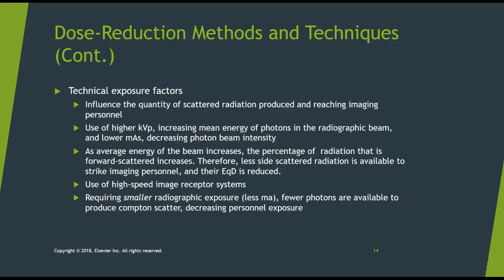Okay, another way you can reduce scatter is technical exposure factors. This influences the quantity of the radiation produced, which influences how much is going to reach you by scatter after it exits the patient. If you use a higher kVp, it increases the mean energy of the photons in the beam, thereby decreasing the amount of scatter radiation coming off the patient. If you increase your kVp, you're going to lower your mAs to compensate, and that decreases your photon beam intensity. As average energy of the beam increases, the percentage of radiation that is forward scattered increases. Therefore, less side scattered radiation is available to strike imaging personnel, and your equivalent dose will be reduced.